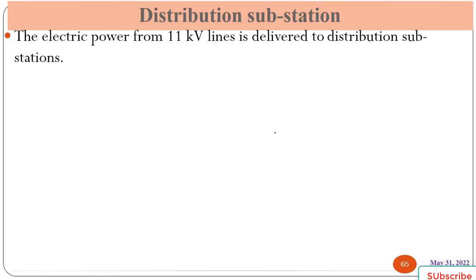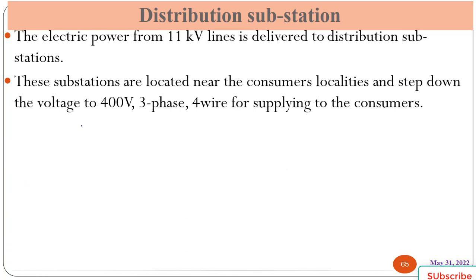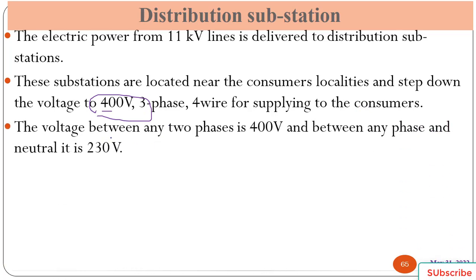The other is distribution substation. The electric power from 11 kV lines is delivered to distribution substations. These substations are located near the consumers and step down to three-phase and single phase. It means 400 volts three-phase four-wire for supplying to a consumer. Thus, the voltage between any two phases is 400 volts and between any phase and neutral is 230 volts.